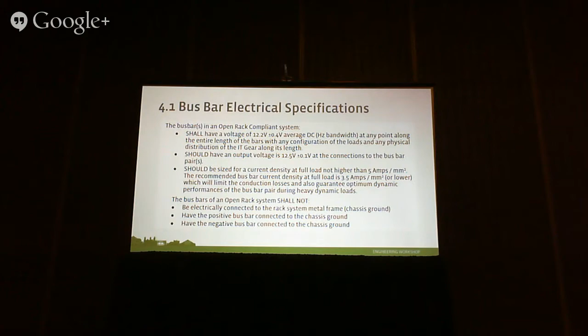So that's the requirement. The way the standard's written out, anything that's a shall is a requirement. A should is kind of nice to have. There's also another level where it just says recommend. In this case, the 12.2 is the requirement. There's also a statement there around the capacity of the bus bar. That's should as opposed to a hard requirement. The last set: bus bars in the open rack shall not be electrically connected to the rack's metal frames, and shall not have the positive bus bar connected to chassis ground or the negative bus bar connected to chassis. This is to eliminate ground loops. So really, it's just that second paragraph. Unless somebody has concerns with that, we can go to the next one.